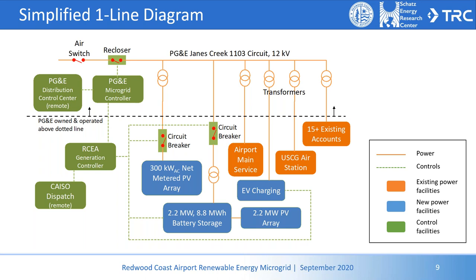PG&E will own and operate the microgrid controller. It controls when the system islands, and if we're in island mode, it's responsible for the quality and safety on the circuit. The RCEA generator controller controls the generators during grid operation, and PG&E has nothing to do with how RCEA operates that during normal grid operation when they're participating in the wholesale market.